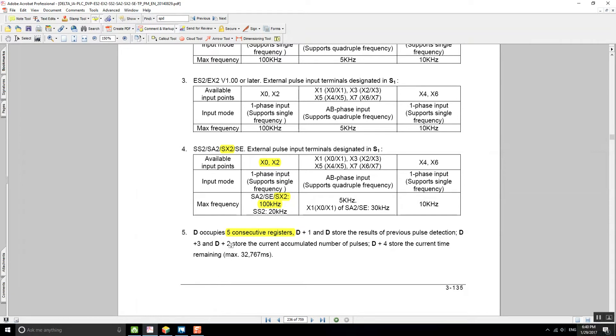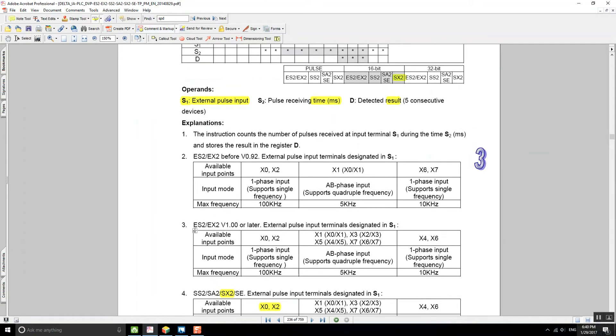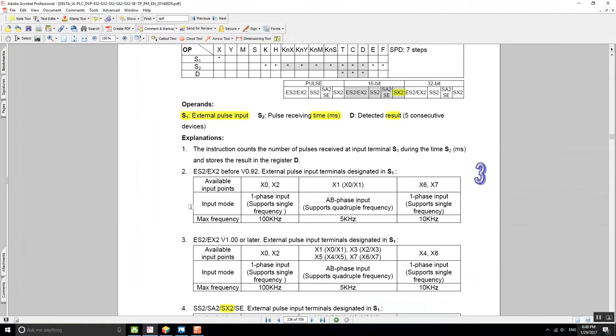D+4 stores the current time remaining. The PLC uses five consecutive devices, so try not to use those for any other purpose. The one that will store the speed result is the very first D device; the other four consecutive devices are used internally by the PLC to calculate the speed.